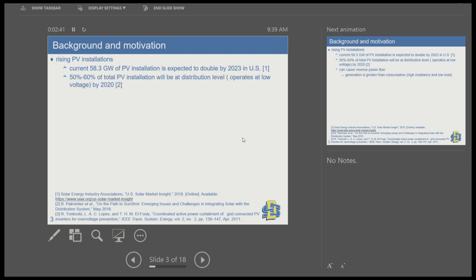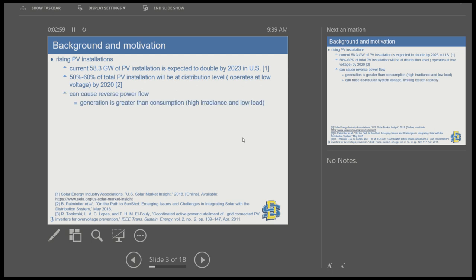These installations are expected to be present at the distribution level. About 50 to 60 percent of these installations will be at the distribution level — that is, operating at a low-voltage level compared to transmission and sub-transmission levels. When there is very high generation instead of consumption, it can cause reverse power flow, and that can cause overvoltage at the distribution level, especially during high irradiance and low-load periods.